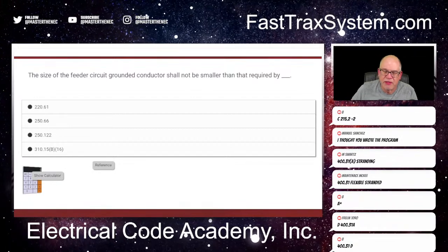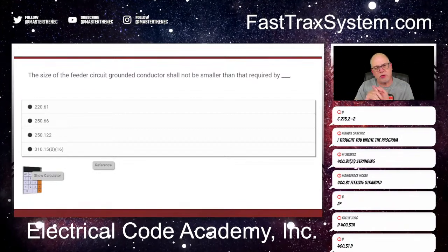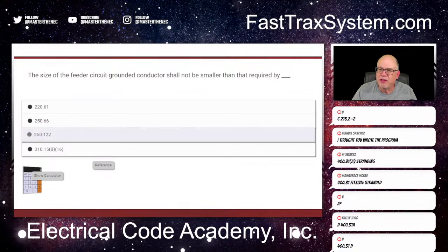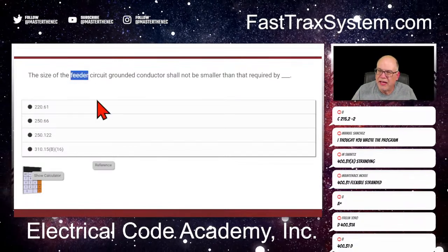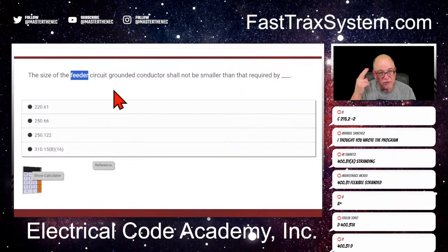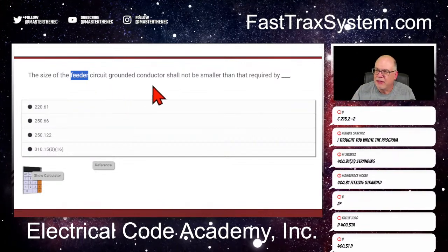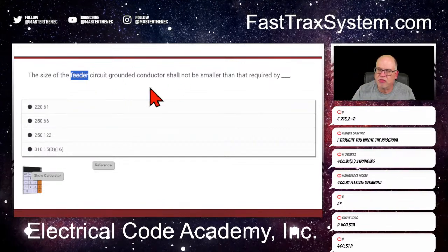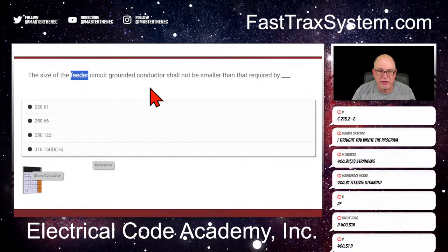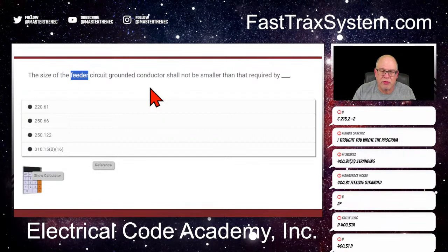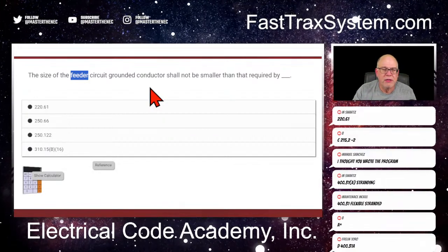So this is talking about feeder. So the first thing that this should kick off to you in your mind is that it's a feeder question. So that is Article 215. It's the first thing that kicks off in my mind. And it's making general statements about the size of the grounded conductor, and it's not to be smaller than this. It's probably going to be larger based on a neutral load calculation, right?